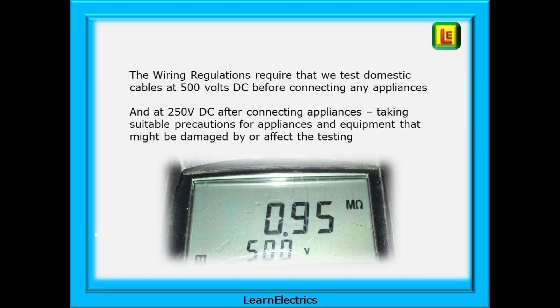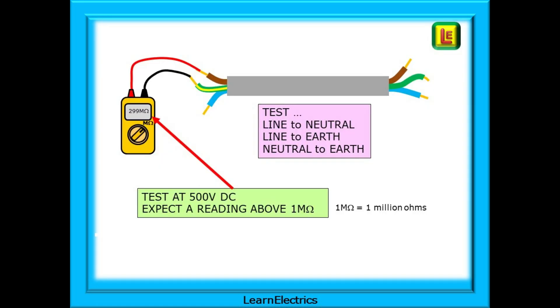The wiring regulations require that we test domestic cables at 500 volts DC before connecting any appliances to the circuit, and then at 250 volts DC after connecting appliances, taking suitable precautions for equipment that might be damaged by the testing. We will test at 500 volts DC between the ends of all the conductors, taking two conductors at a time. The test meter is connected at one end and the other end is left open with no connector blocks. For single phase circuits we will test the three combinations of line to earth, line to neutral, and neutral to earth, expecting a high ohms reading each time - above one mega ohm or one million ohms. With a new installation we should expect readings that max out the meter: 200 mega ohms on my meter, 500 mega ohms on others and even higher.